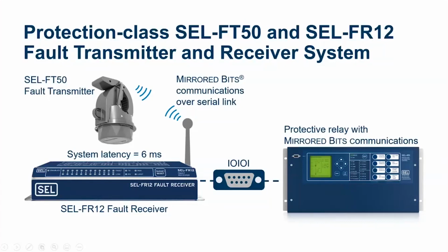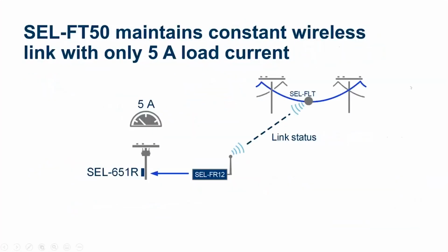The FT50 takes about 2 milliseconds to detect a fault and send a signal to the receiver. Then the receiver takes about 4 milliseconds to send the signal from the receiver to the 651R. It uses serial protocol or mirrored bits protocol over serial to send the information, whether this is in a trip state or a non-trip state. So it can send a signal over serial to the relay. It overall adds a minimum of 6 milliseconds to your decision logic. So you can enable or disable reclosing based on what information you get from the fault transmitter. Again, as I mentioned, it needs 5 amps of load current to develop a link status between the FR12 and FT50.